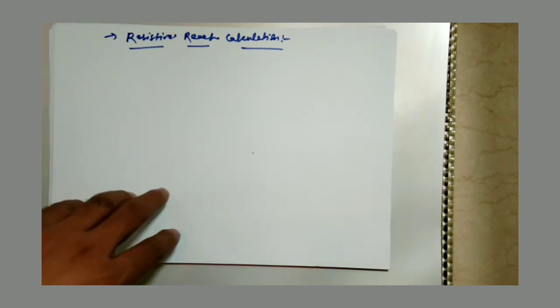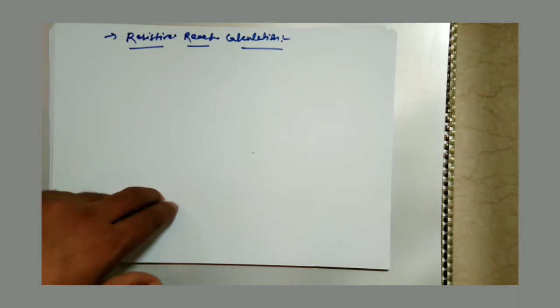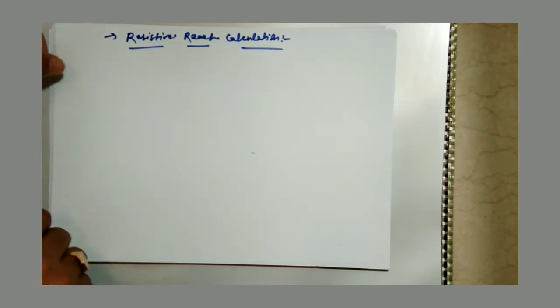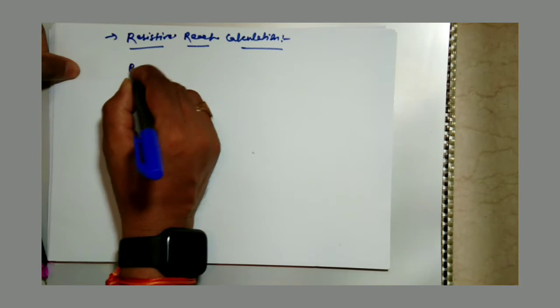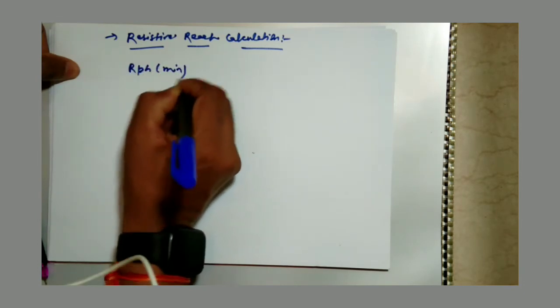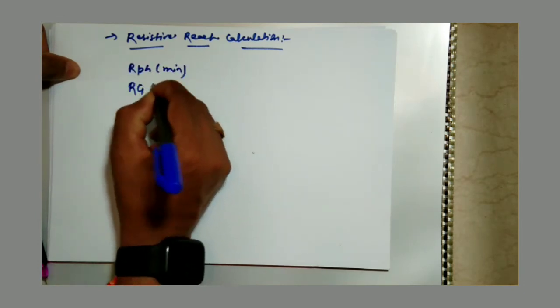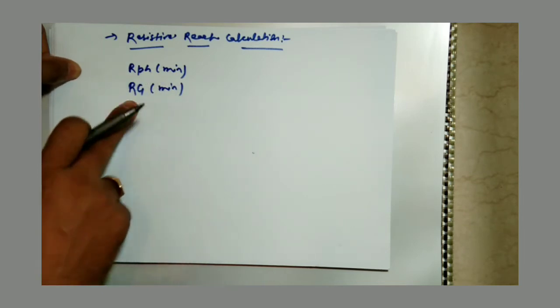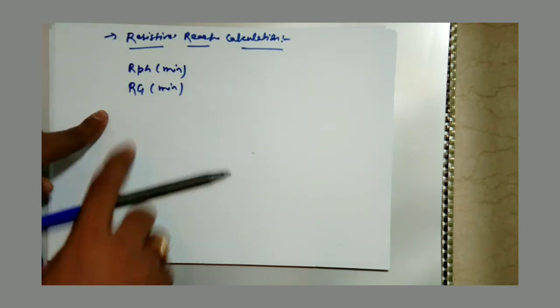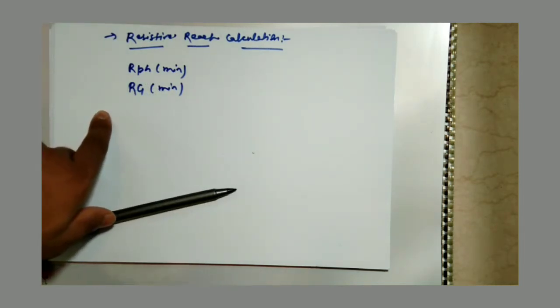Normally resistive reach is calculated using the typical arc resistance calculated by the Van Warrington formula. In the table you have to check for the resistive coverage, and accordingly you set the value for the R phase: resistive reach phase to phase minimum, RG minimum, phase reach phase to ground. So normally you will get the value from that table.